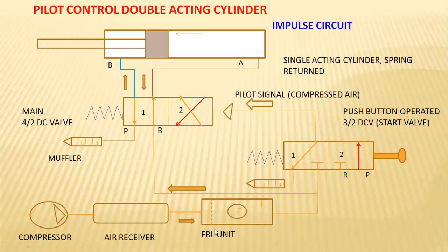So here normally the compressor allows the compressed air, which causes this FRL actuation, and will allow the normal flow of the compressed air that enters from side A, which tends to move this piston towards the forward direction, and the released air is released towards the atmosphere from B to P. So the forward action continues without operating this main DCV, because that main DCV is spring return in the first position, which is commonly connected towards the forward movement of this cylinder and piston arrangement.